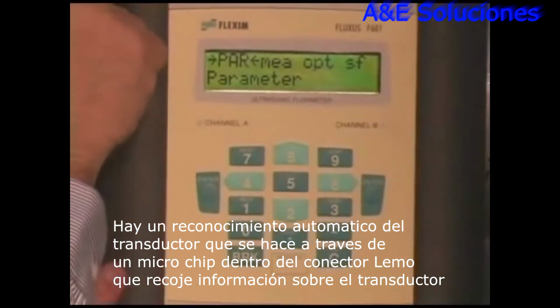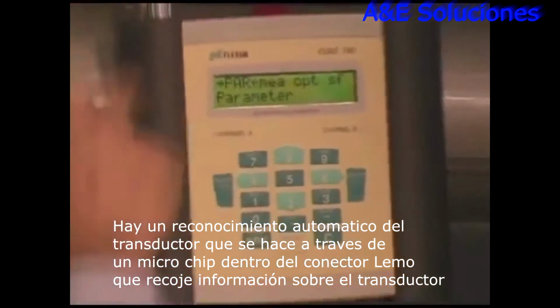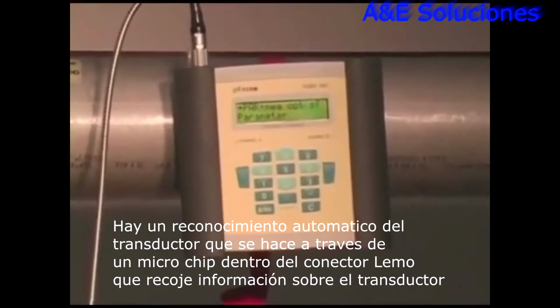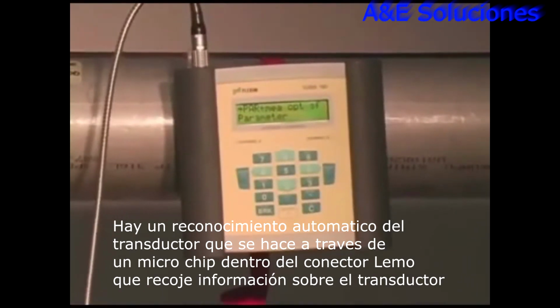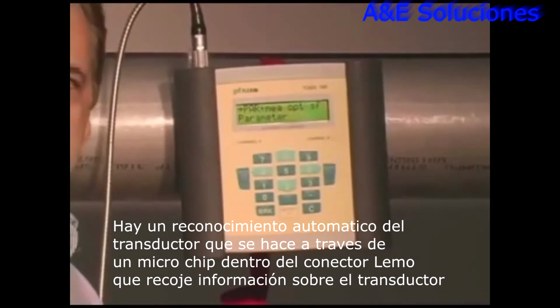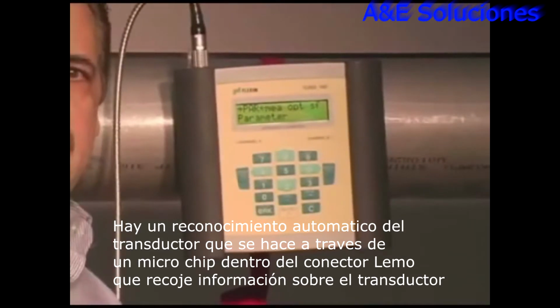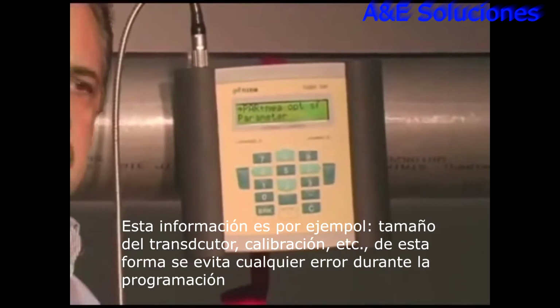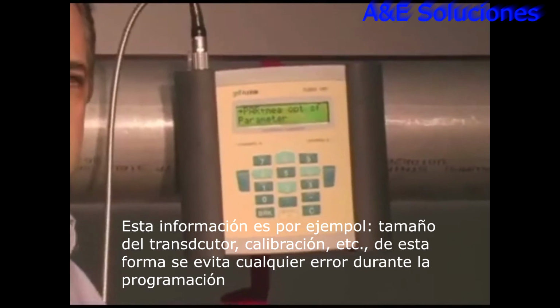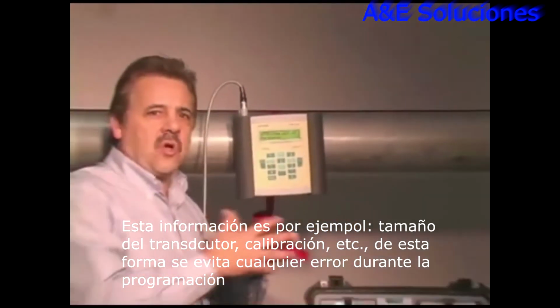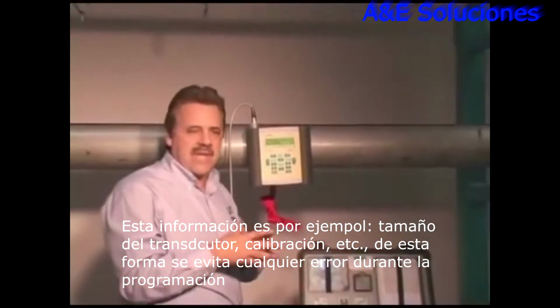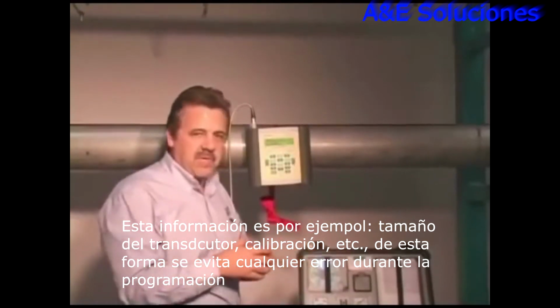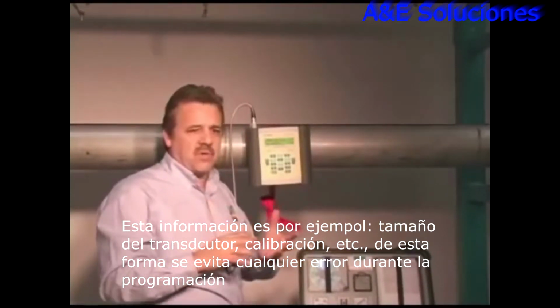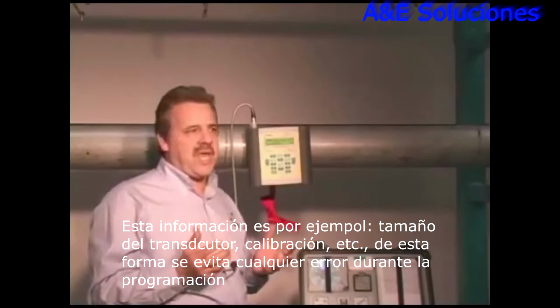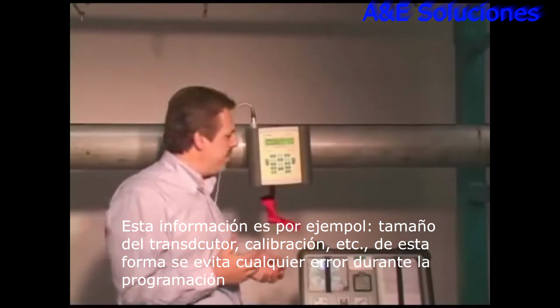Inside this LEMO connector here, there's a micro chip, what we call a SENSPROM chip, and that SENSPROM chip contains all of the information about the transducer, as well as its calibration information and what size transducer it is. So it both installs the calibration data for that transducer and tells the meter what transducer you're using. So that's one of the things you can't make a mistake on when you're programming the meter as well.